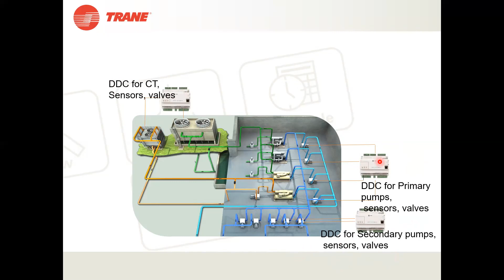We are putting a controller over here along with the primary pump side, along with sensors, valves, etc. Similarly, we are putting DDCs in the secondary pumps along with sensors, valves, etc., and also controller, sensor and valves along with DDCs at the cooling tower side. So now all these three systems are controlled individually through these DDCs, but if I have to control the complete system, I will be putting one master controller with licenses.